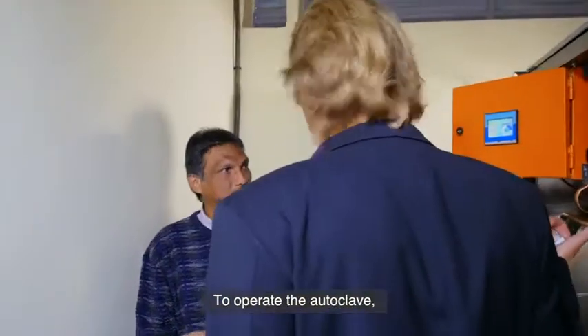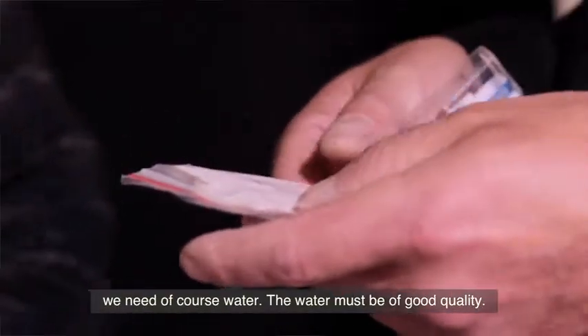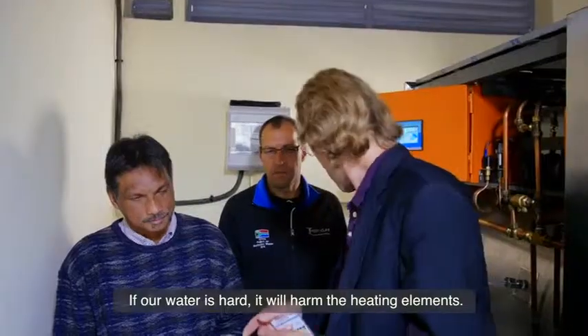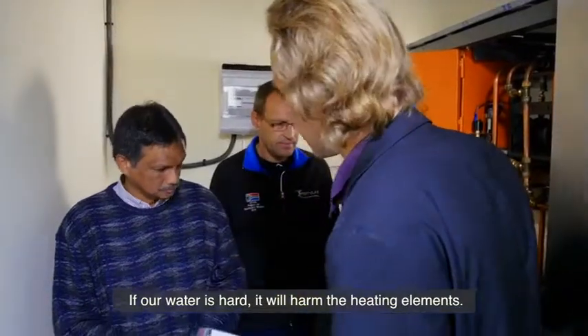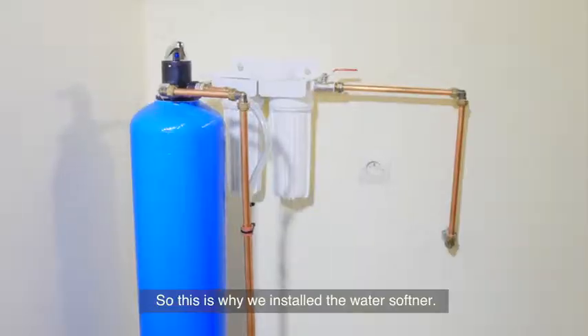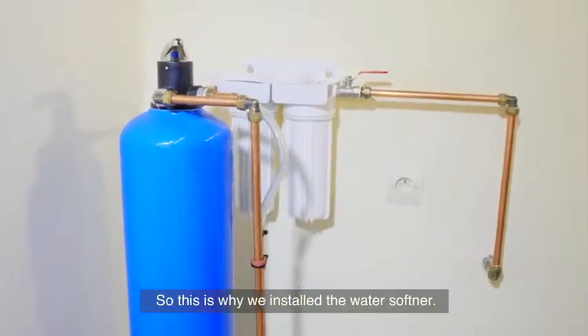To operate the autoclave, we need, of course, water. The water must be of good quality. If our water is hard, then it will harm the heating elements. So this is why we installed the water softener.